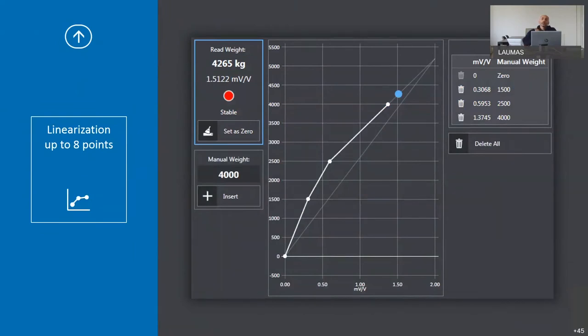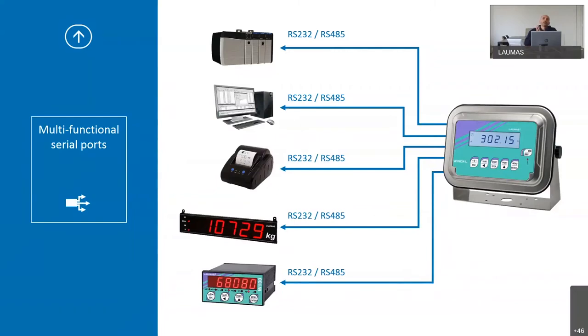Here we can see the linearization and the sum of the eight possible correction points. We can also see the possibility to connect different devices to the serial port, such as a PLC, a PC, a Laumas printer, a Laumas large display. You can also connect the same or different indicators as master or slave, and they could be used as a remote display.